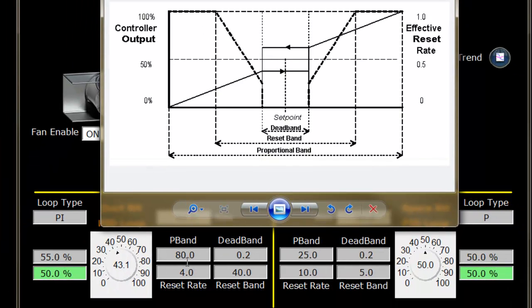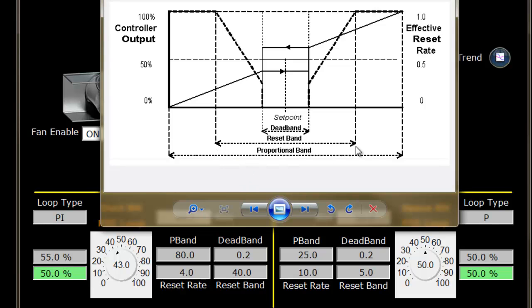If you remember, we already looked at the proportional band and the dead band. Now we're adding the reset band. I always like to make the reset band half of the proportional band. In this case, if our proportional band is 80, I make the reset band 40. The graph would look like this—80 span here and a 40 span for your reset band.